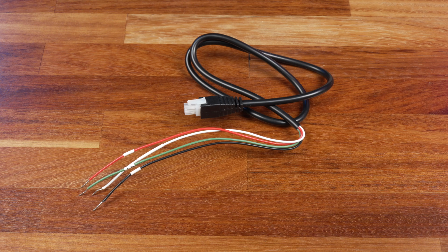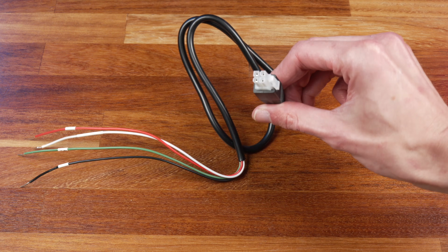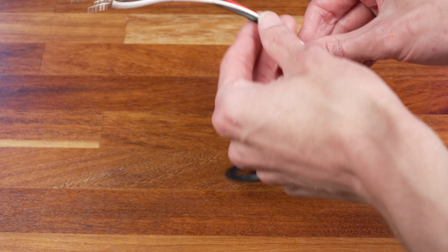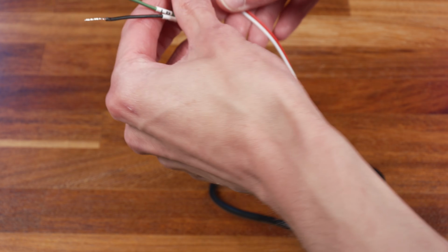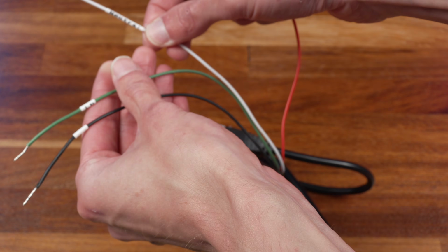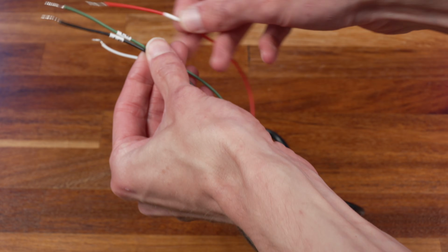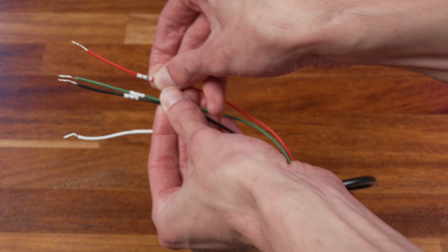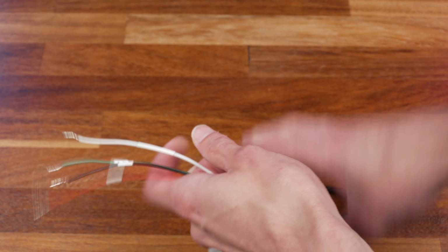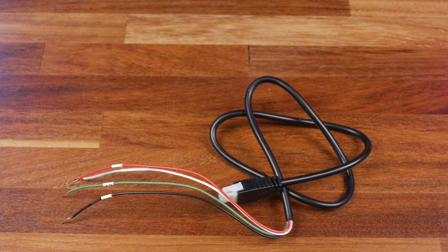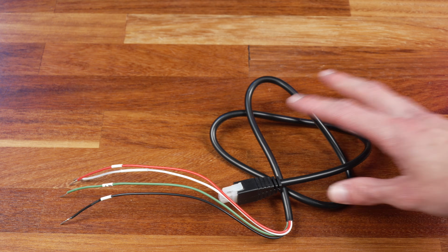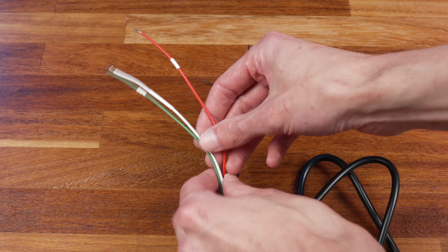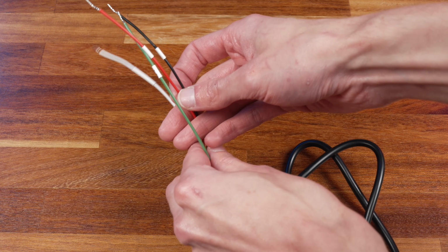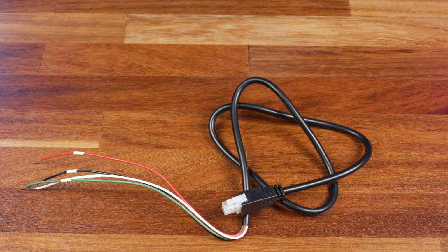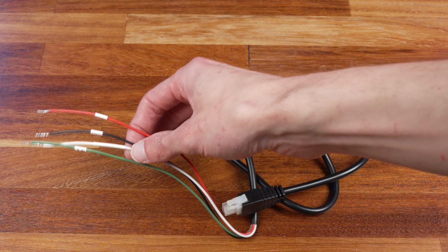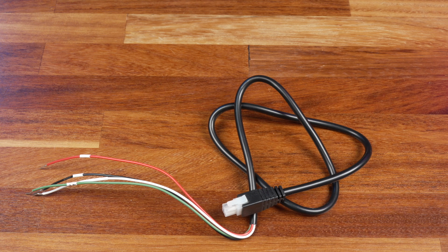This cable connects to the energy monitor with this 4-pin connector here, and then we have four different wires that come out. You can see the labelling: we have neutral, we have LA, LB, and LC on these wires here. And that's because this device can work with systems with anywhere between 1 and 3 phases. So on a 3-phase system, you connect each of these live wires to each of your phases. On a single-phase system like I have here, you'll just connect all these up to the same line or live conductor, so they'll all just essentially measure the same phase.